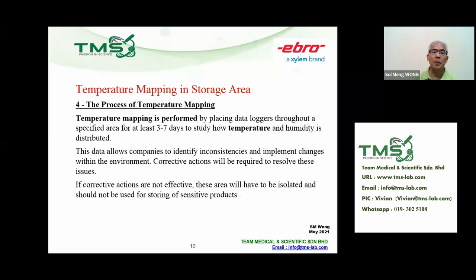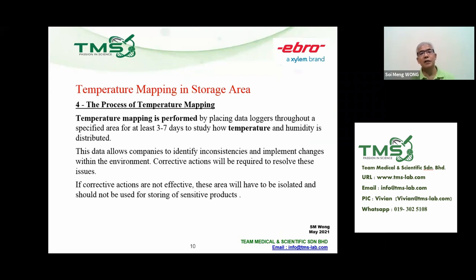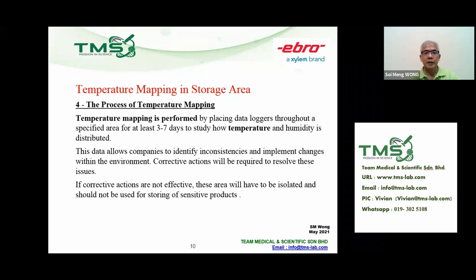How is the temperature mapping process performed? Temperature mapping is performed by placing data loggers throughout a specific area for at least three to seven days to study how temperature and humidity are distributed. This data allows a company to identify inconsistencies and implement changes within the environment. Corrective action will be required to resolve issues; if corrective actions are not effective, the area should be isolated and not used for storing sensitive products.